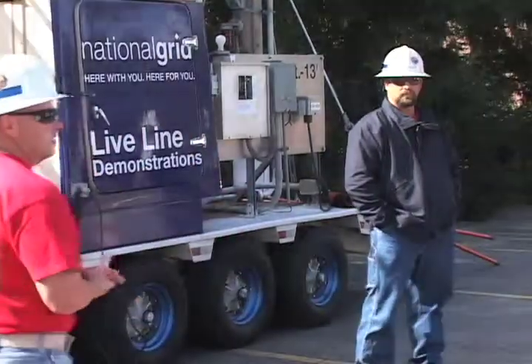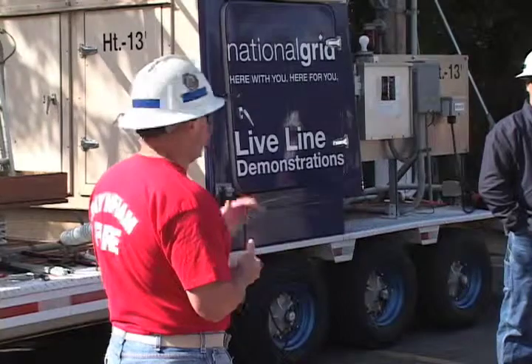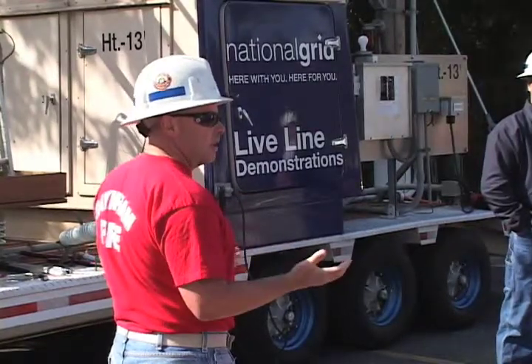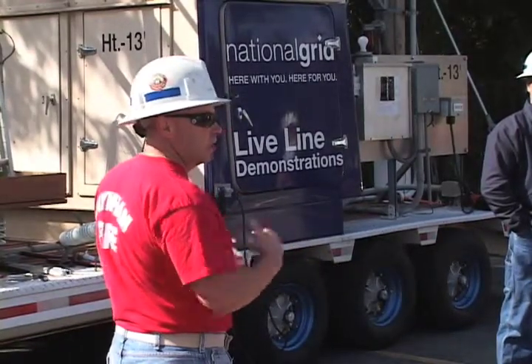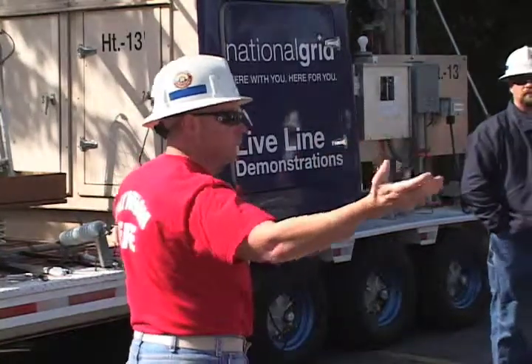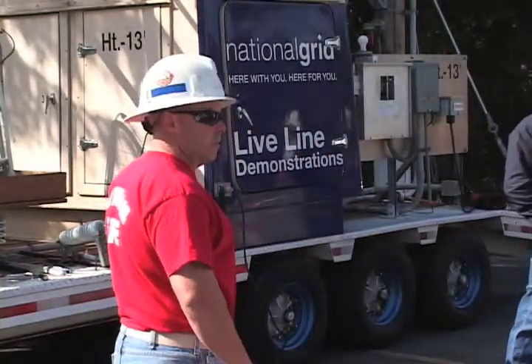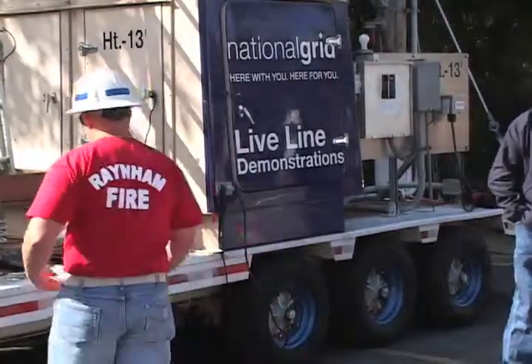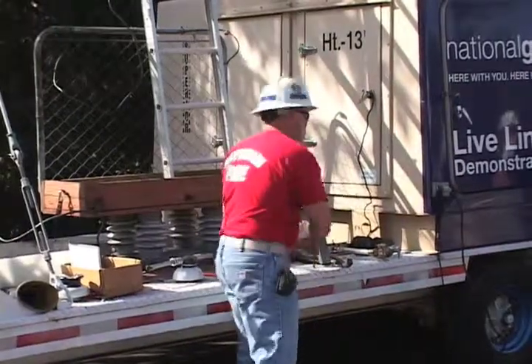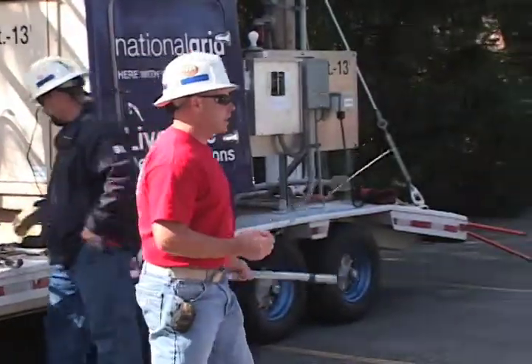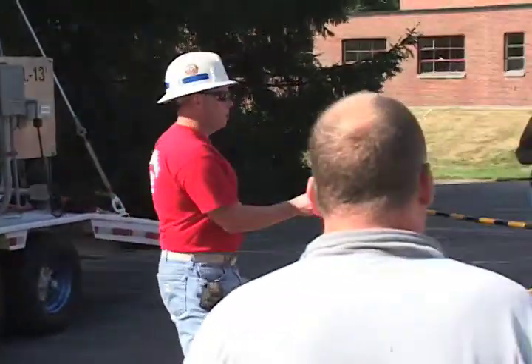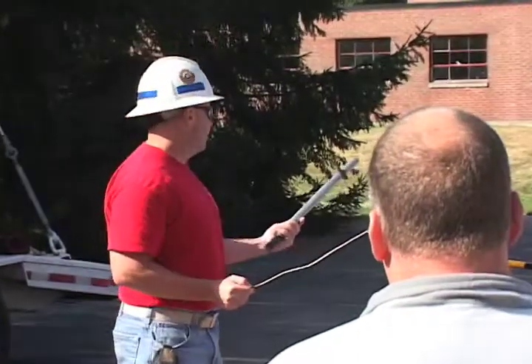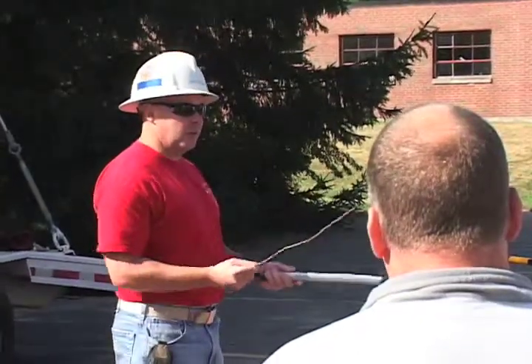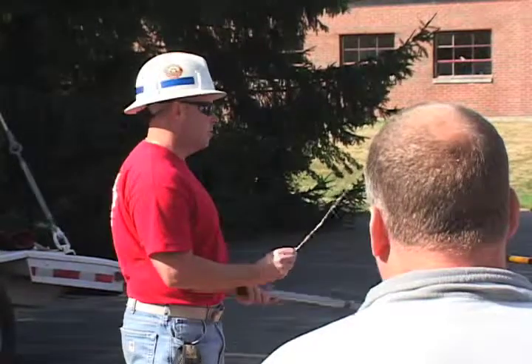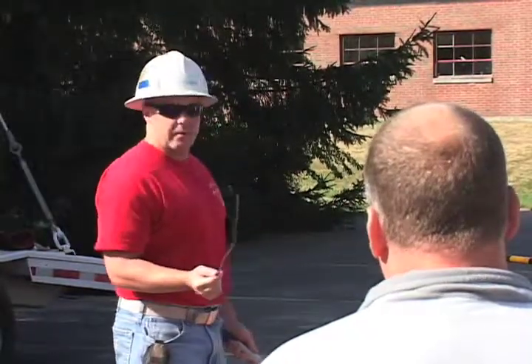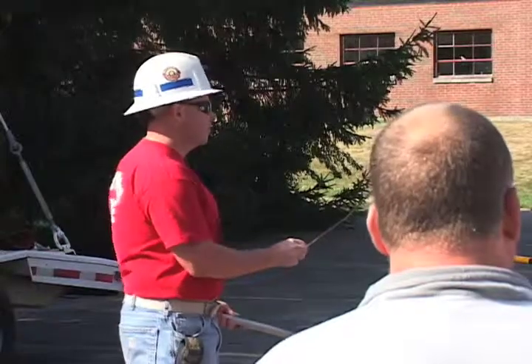What we have here is the real deal. We're producing electricity with this generator, it's not make-believe - we can't produce the amperage like we have out on the main road, but we are producing about 8,000 volts of electricity. So with that, I've got some show and tell. Everybody thinks big wire, big power - that's not true. This little piece of number 6 copper can carry the same voltage as this piece of 477. So don't think little wire means little power - that's not true, because we do use this wire as a primary conductor at 8,000 volts.